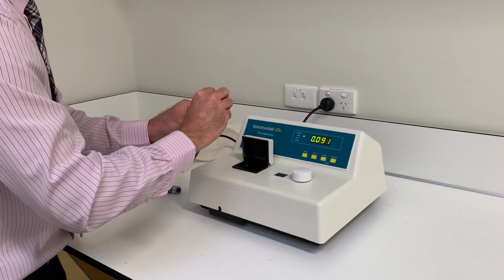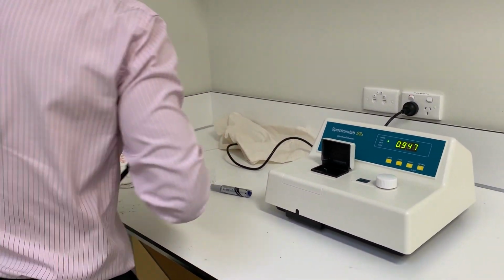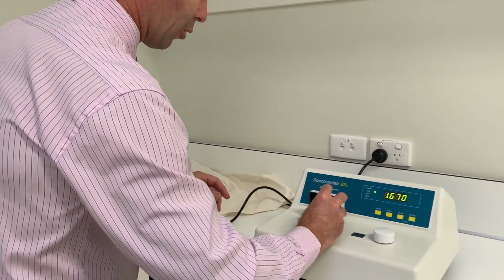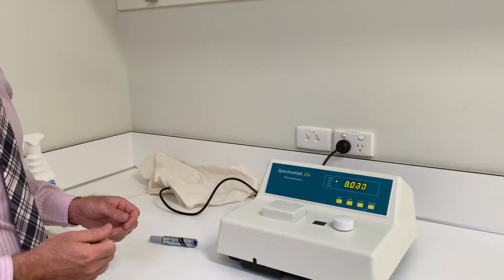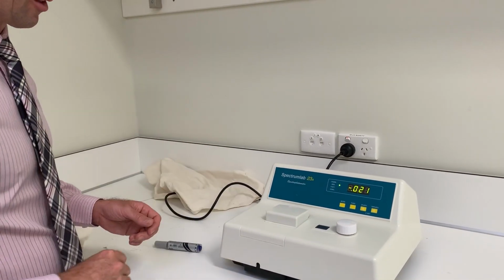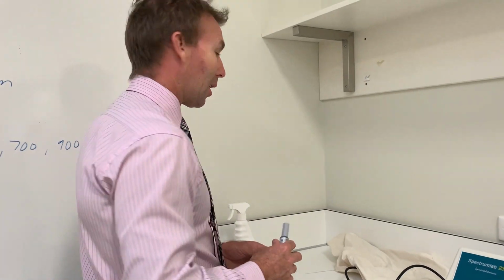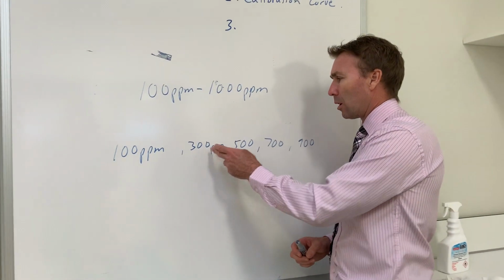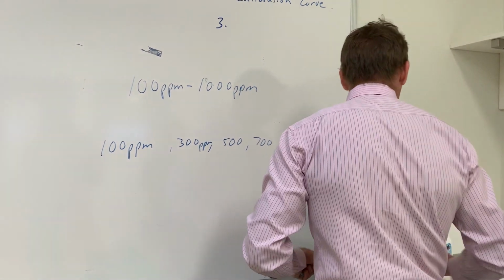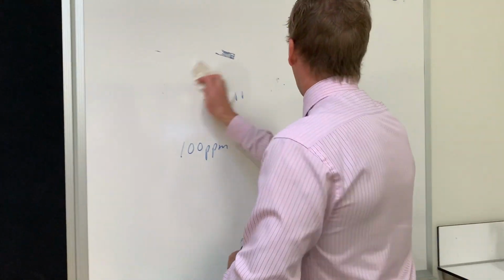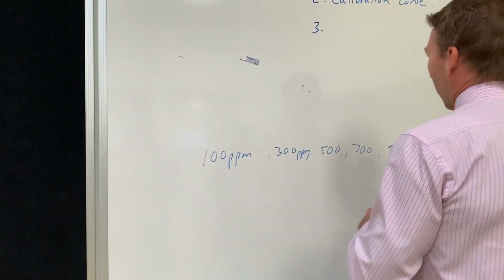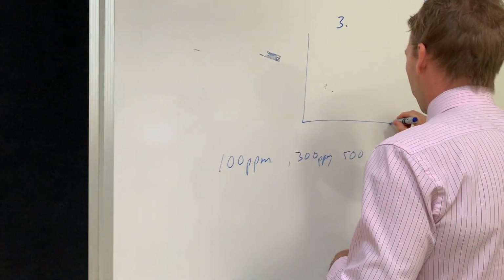And then what you do is you get your 100 ppm solution, you put your 100 ppm solution in, you get a reading. This is going to go back, it's drifting a lot, isn't it? You put your 100 ppm solution in and you get a result. You put your 300 in, you get a result, etc, etc. And then once you've got that, you'll end up with a graph that looks something like this.